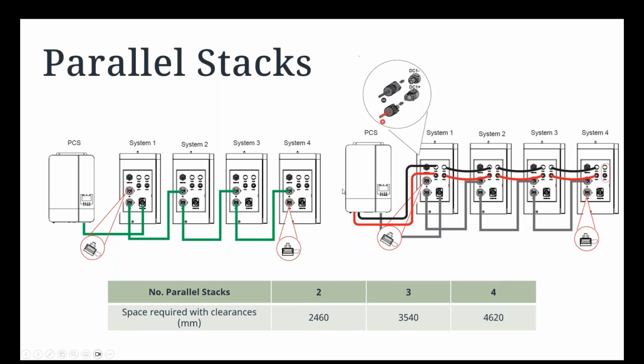For the power connections, you'd go from your GEN24 Plus battery plus and minus terminals directly to the plus and minus terminals of the Reserva 1, then going out on the second ports and wiring them through. We have the space required clearances on the bottom and top, which the next slides will show in more detail regarding distancing between units. Another question that might arise is putting towers back to back or front to front - we're actually investigating a solution for a nice setup in limited space scenarios.